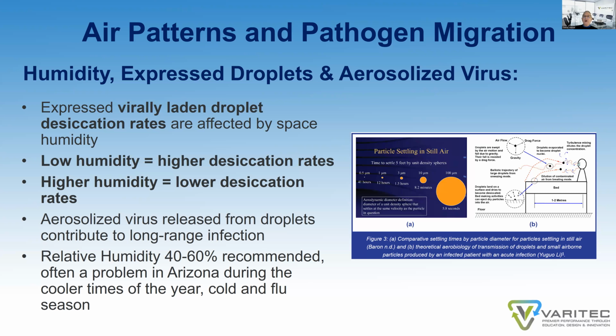So anyway, let's look at what influences the risk of infection. And one could argue, perhaps even contaminants within a space, as indoor air quality is getting more and more attention today. Anybody who is sick, who coughs and sneezes, or even breathes in a room expresses virally laden droplets. And if these droplets are ejected into a room that is not properly humidified, those droplets desiccate very quickly. The water in the droplets evaporates within a couple of seconds, releasing any pathogens that might be in that droplet into the air. And those desiccated viruses are lighter, they are buoyant, and they will stay in the air for a prolonged period of time, 24, 48 hours, possibly even more.